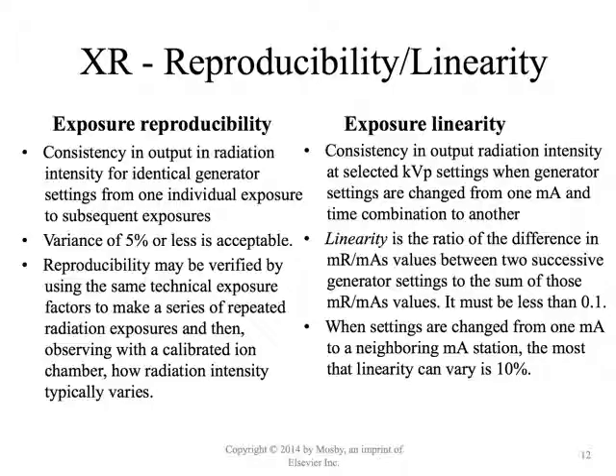Linearity is what happens if we start changing the mA and the time settings, but we're always going to shoot it at some amount. Again, 2.5 mAs, but that might be varying mAs or varying times. We want something that's fairly linear, right? And so when the settings are changed from one mA station to the next, but resulting in the same mAs, the linearity should be within about 10%. It shouldn't be more than that.